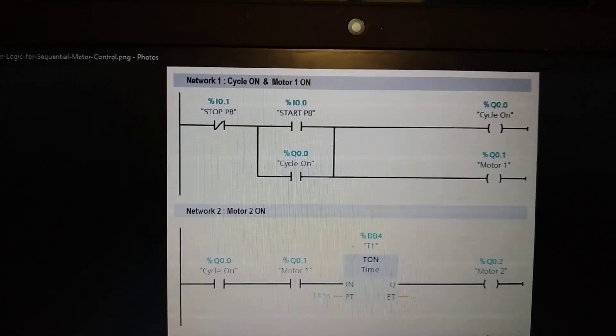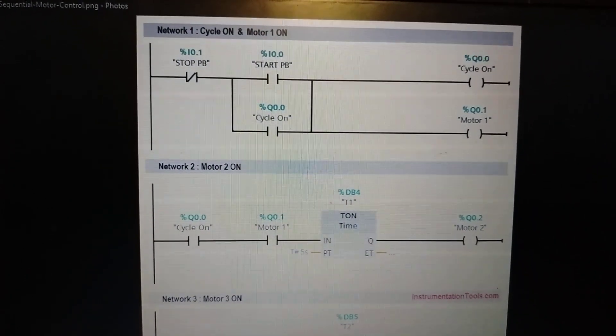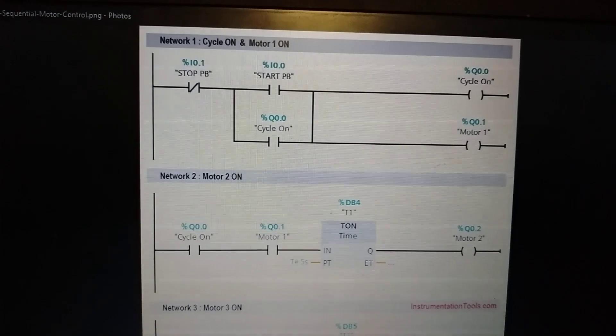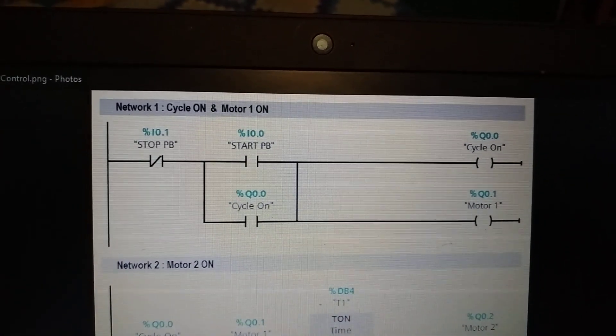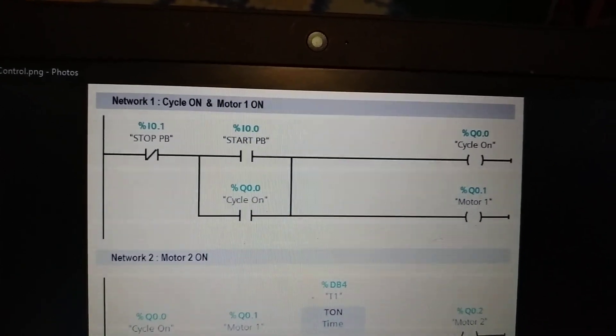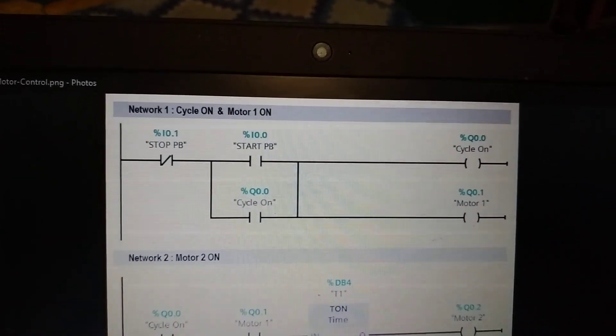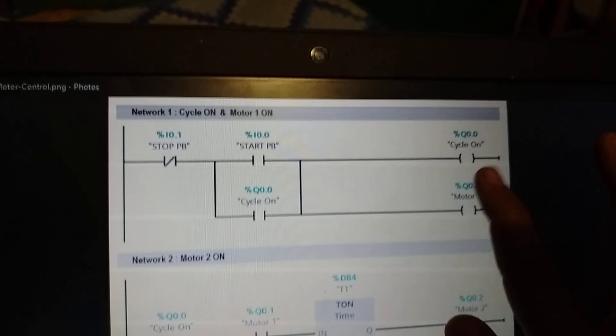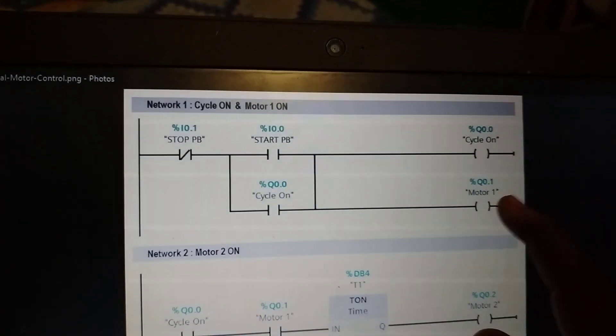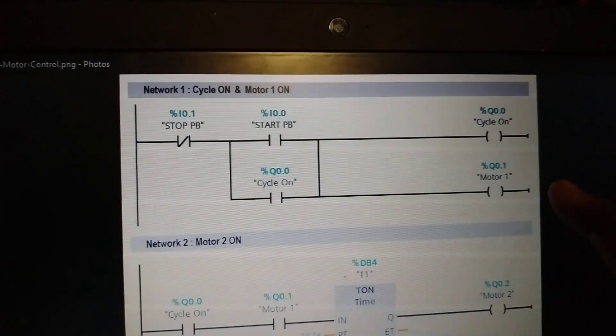This ladder logic for sequential motor control is divided into three networks for understanding. In network one, we have a start push button and stop push button connected serially to the cycle on coil. When the start push button is pressed, cycle on will turn on, which in turn makes motor one turn on. The loop then continues.